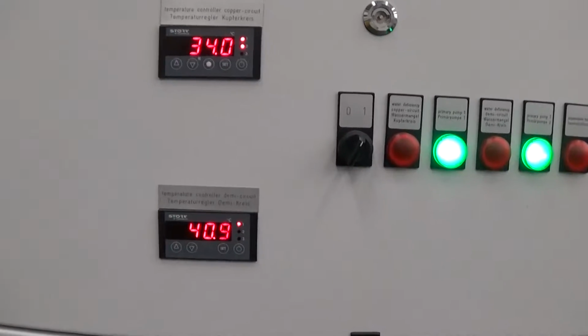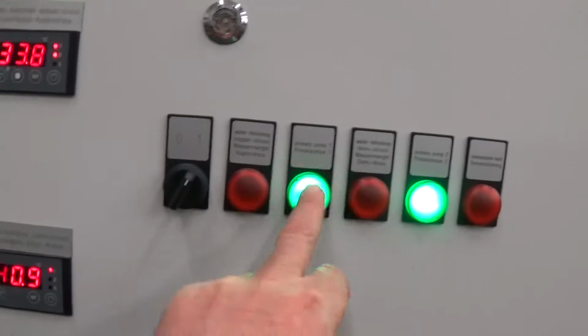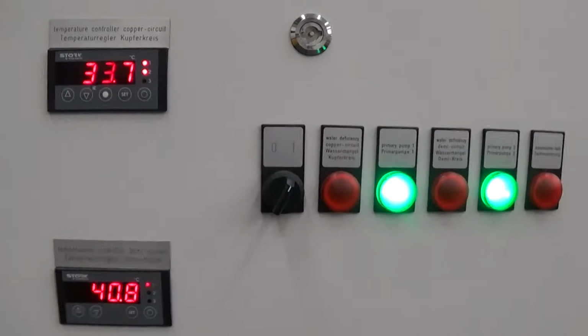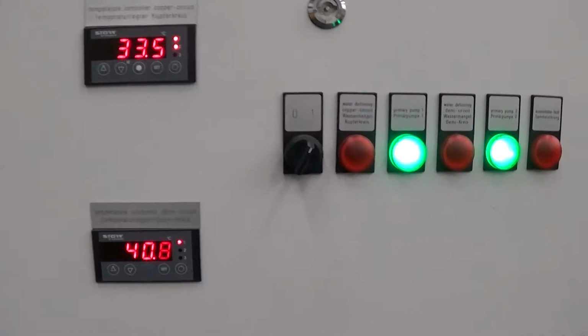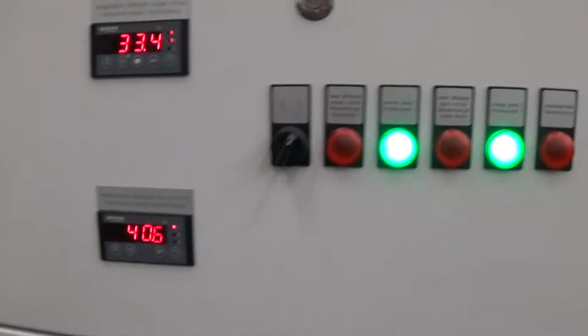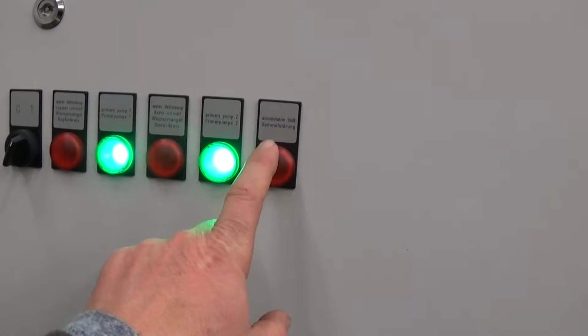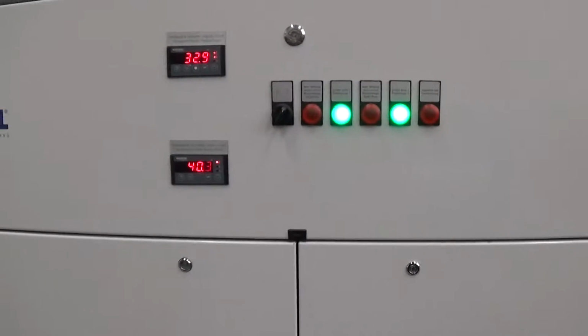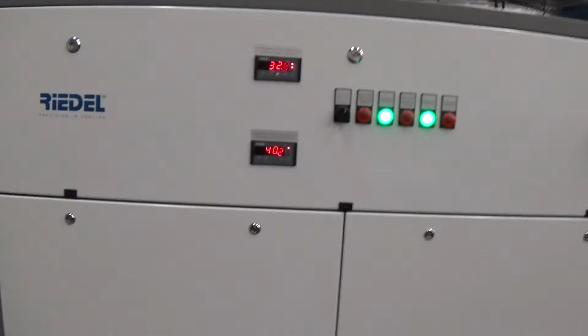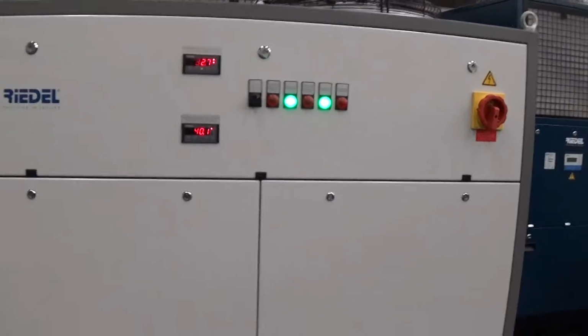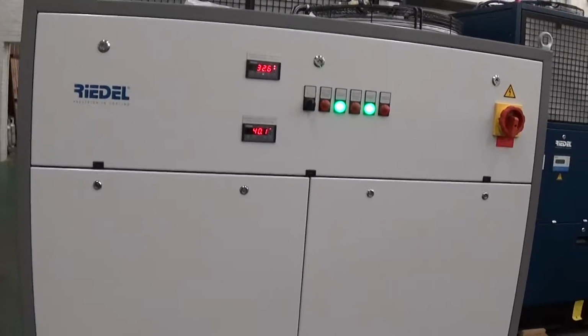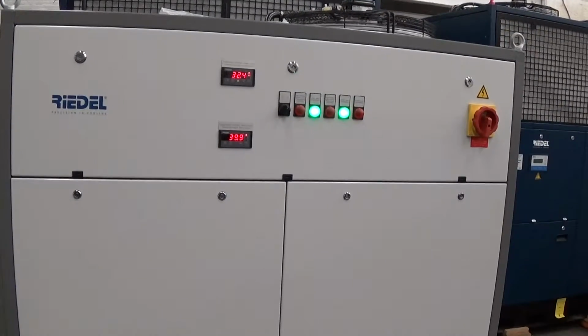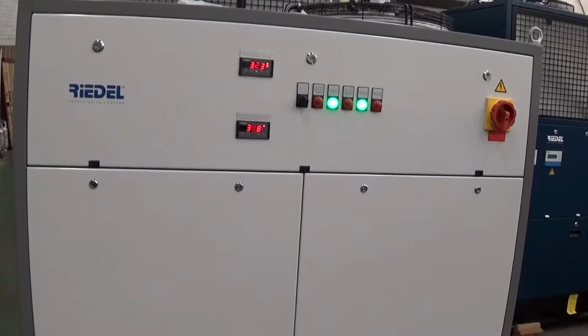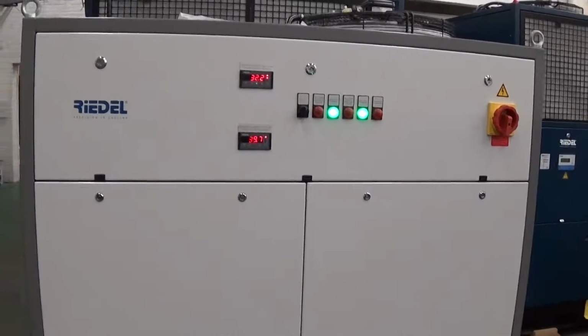Simple to start and run. Basically, you just turn the unit on and both pumps come on. If there is some type of error or fault, or like a pump were to overload or trip out, you'd see something here in the accumulative fault. The only times you really see pumps tripping out is if there's not enough back pressure in the loop, but running through a laser should be more than fine. Pumps like to have some type of back pressure or load on them.